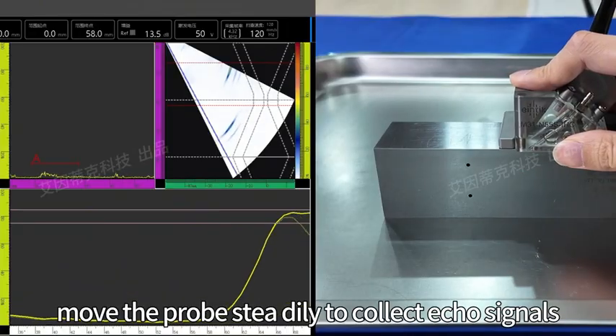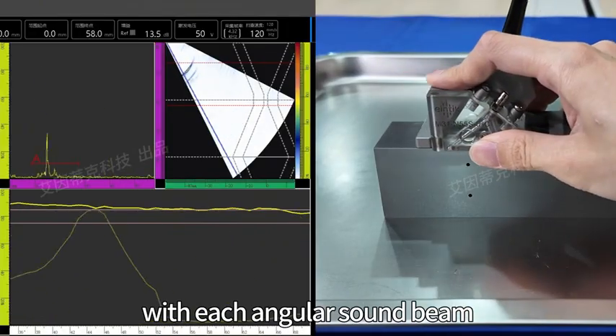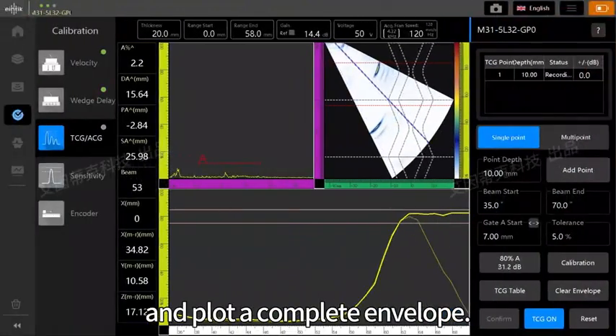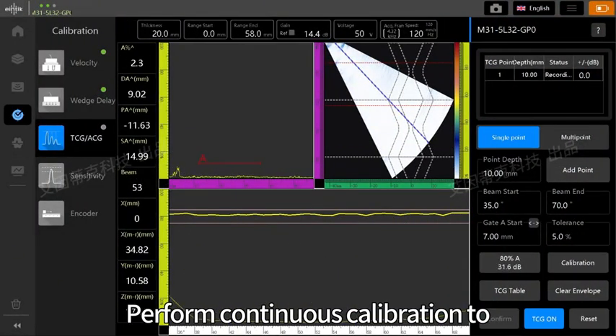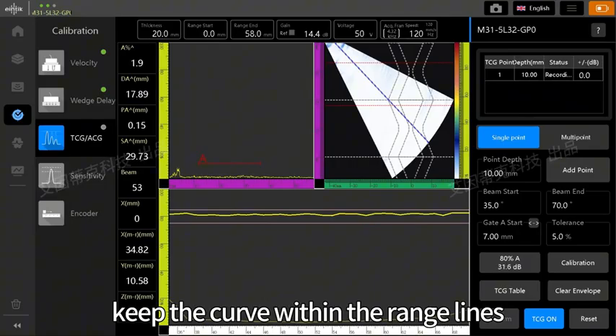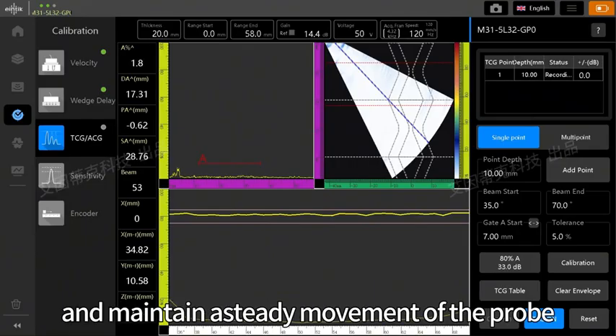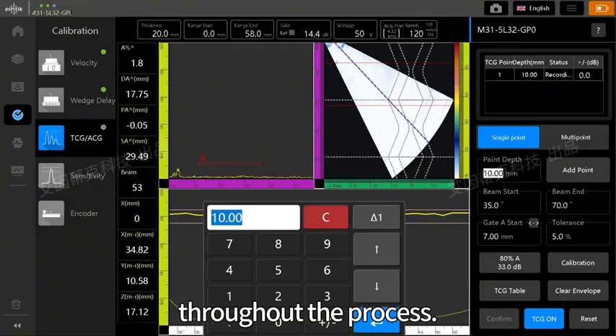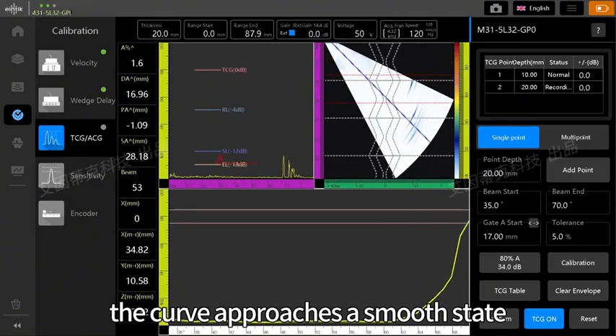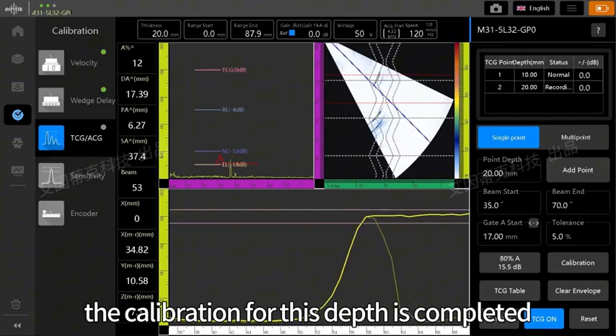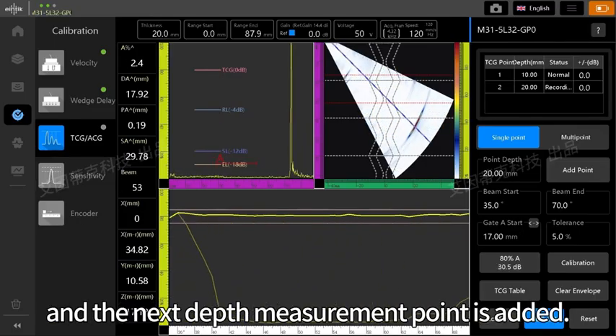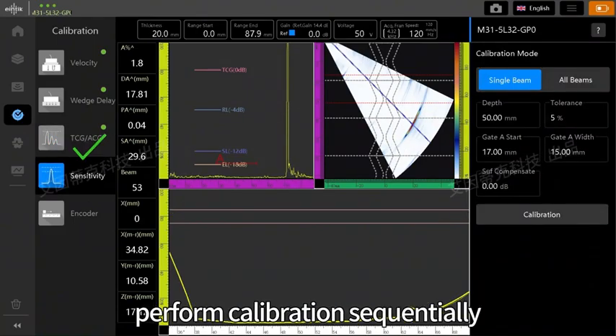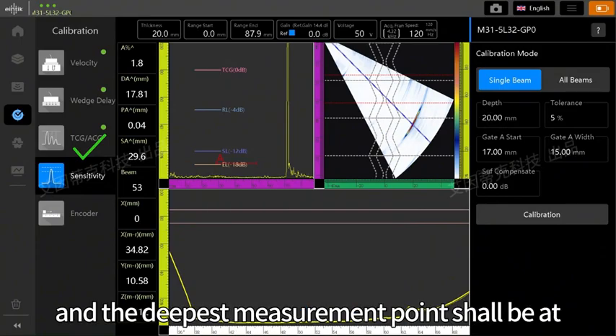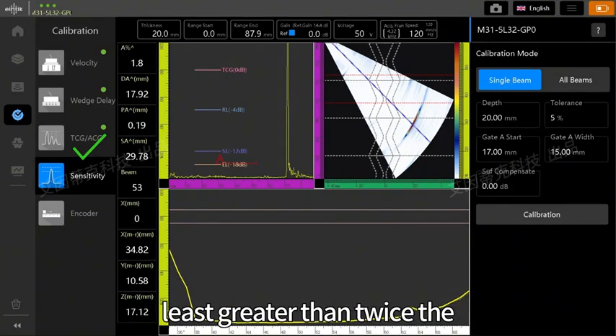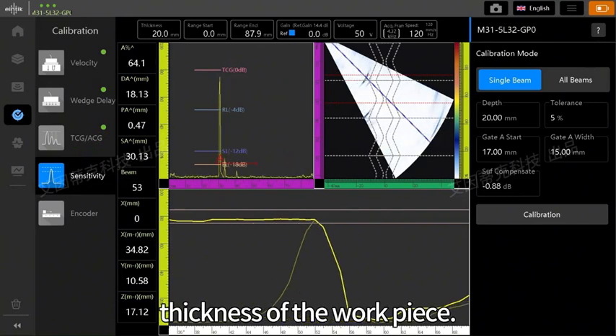Move the probe steadily to collect echo signals with each angular sound beam, and plot a complete envelope. Perform continuous calibration to keep the curve within the range lines, and maintain a steady movement of the probe throughout the process. At this stage, the curve approaches a smooth state. The calibration for the depth is completed, and the next depth measurement point is added. Repeat the above procedure to perform calibration sequentially, and the deepest measurement point shall be at least greater than twice the thickness of the workpiece.